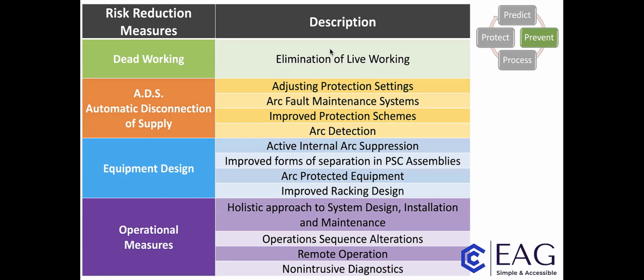The others I won't have time to go through today, but improved protection settings and arc detection all come under automatic disconnection of supply. Arc detection works by picking up the light that's emitted from an arc internally in switchgear, then looking at the rising current and disconnecting very quickly. Equipment design follows on from that. The active internal arc suppression does everything arc detection does, but it also clamps a short circuit across the busbars and sometimes to earth as well. It's very quick acting, we're talking about 4 milliseconds from the initial arc itself.